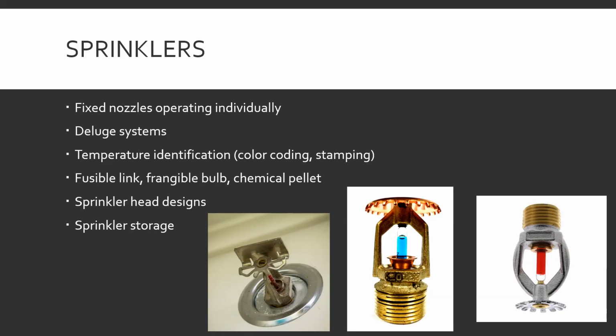Actually, we'll go back. I don't have pictures of them, but there are also different ways sprinklers come. So, for example, there's concealed sprinklers. These are in like your apartment buildings, newer hospitals, fancier places where the builders don't want people walking down the hallway to look up and see all these guys hanging down. So they'll have like little white plastic caps over them so that when the sprinkler goes off, the water comes out, pops the cap off. The sprinkler can do its job, but the average guy walking down the hallway at 2 in the afternoon isn't going to look up and go, oh, there's a sprinkler head there.